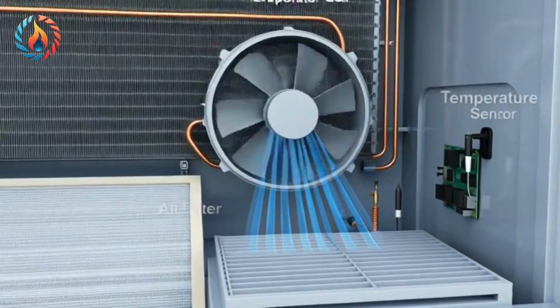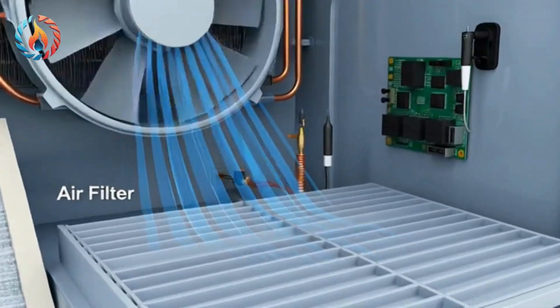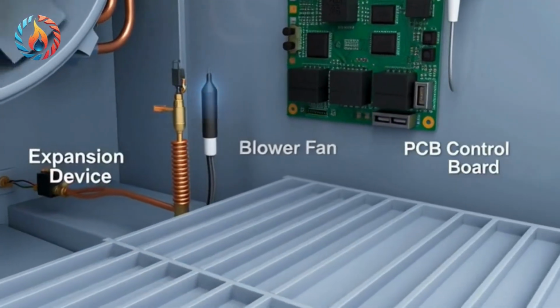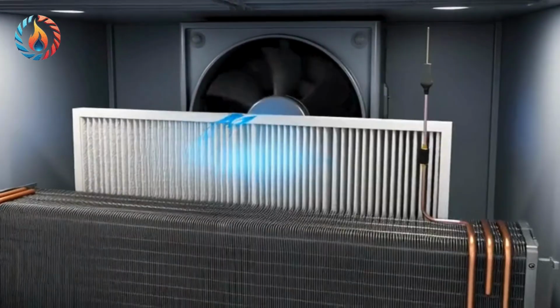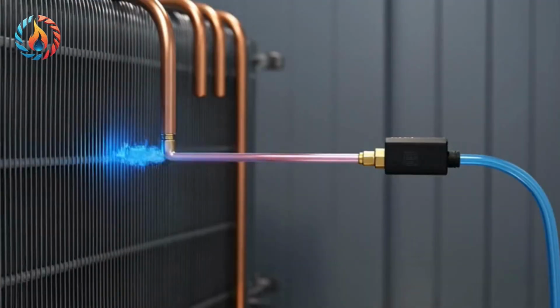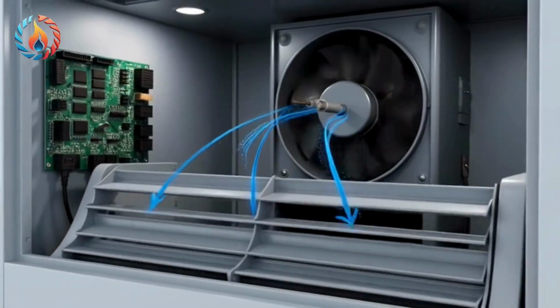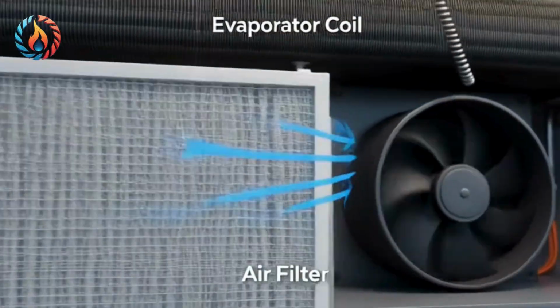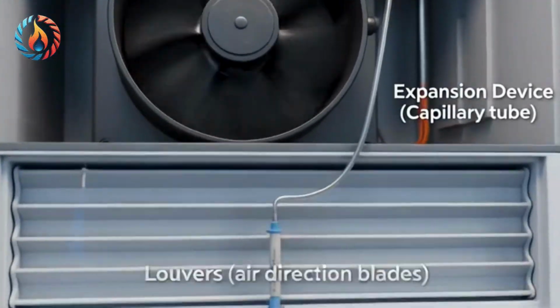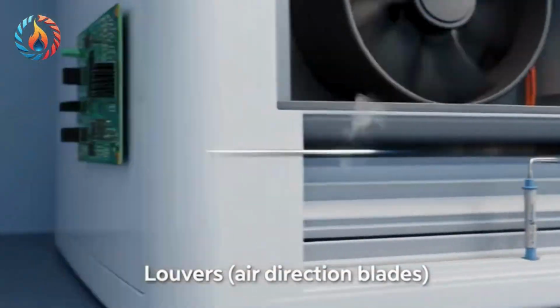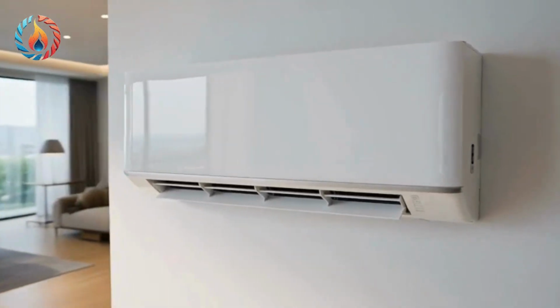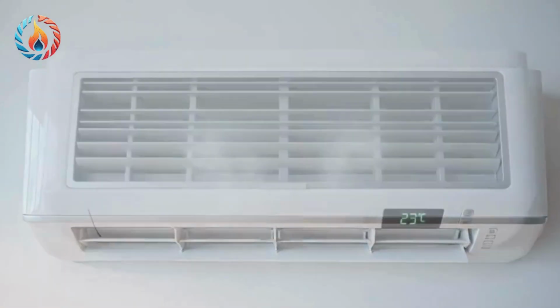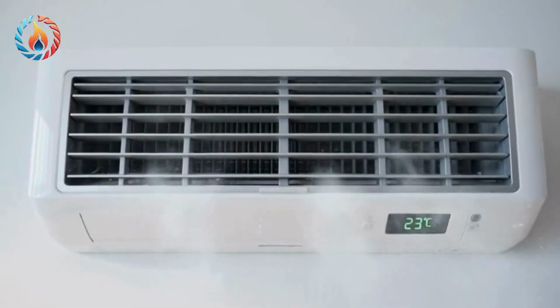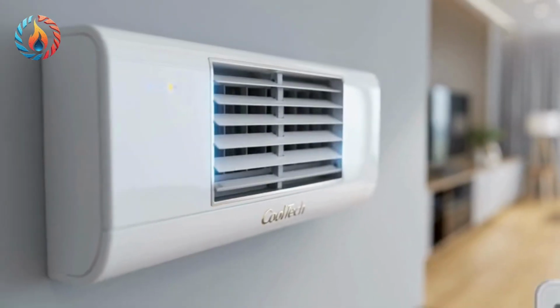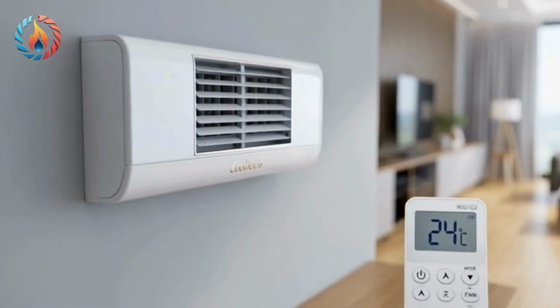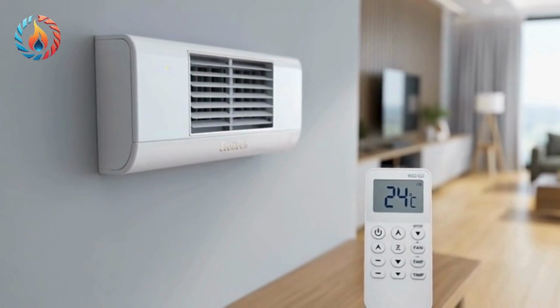The indoor unit contains the evaporator coil, air filter, blower fan, expansion device (capillary tube or electronic expansion valve), louvers, air direction blades, temperature sensor, and PCB control board. The evaporator coil absorbs heat from the room air. The blower fan pulls warm air from the room, passes it over the cold evaporator coil, and then pushes cooled air back into the room.